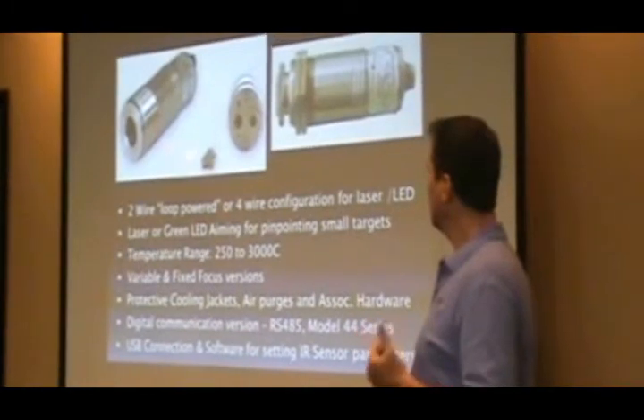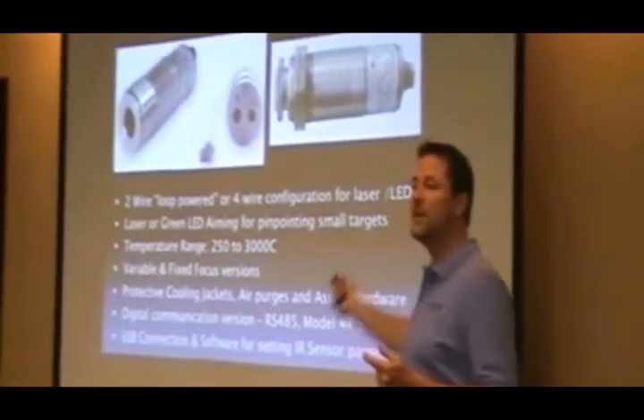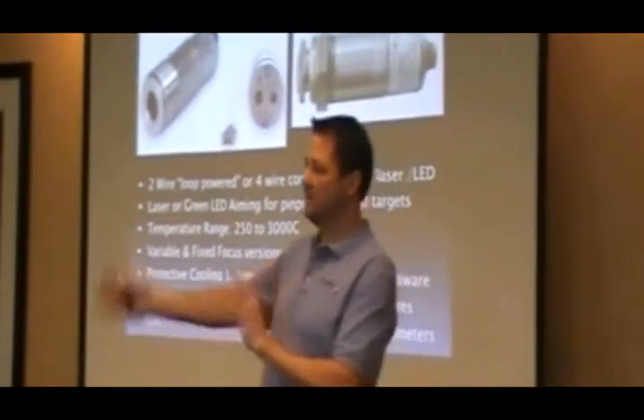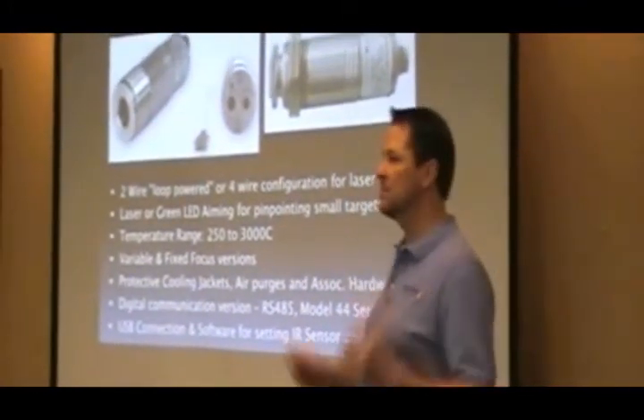The units have 4-20mA output, or you can get a version with the 44 series — a DG44 or DS44 — and it'll have RS-485 in case you want to daisy chain, say, 32 pyrometers and address each one in a PLC system.